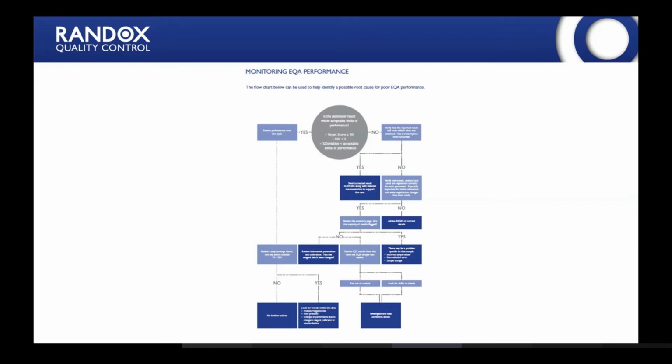In some cases we're saying on our EQA reports that, okay, looking at 2 standard deviations, that may be a trigger point for yourselves, but you may only look at taking some form of corrective action if you have 2 results in a row outside 2 SDs, where you start looking at multi-rule aspects. But this will be really determined by yourself.